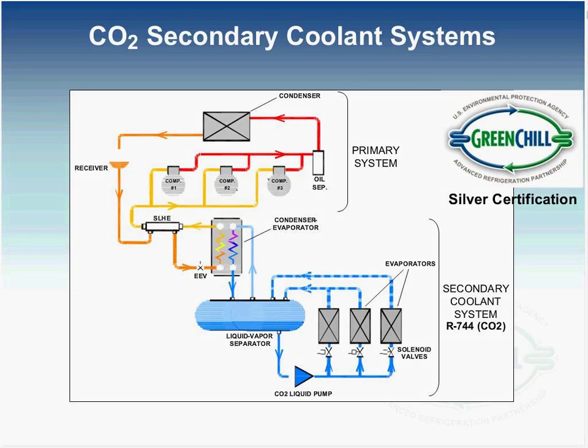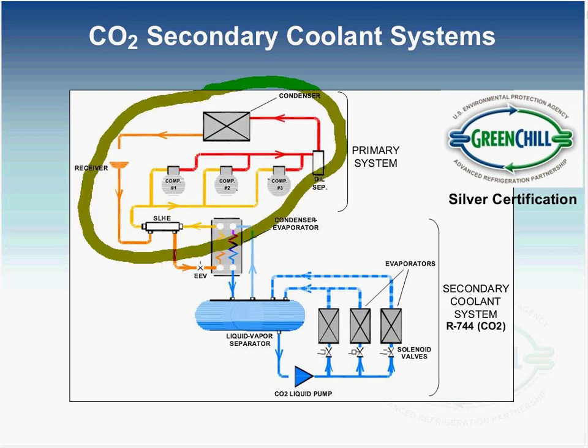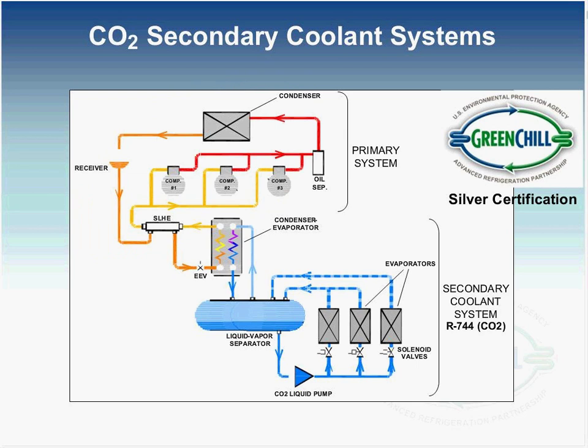So we'll start with a piping schematic here of what the system looks like. In the upper left-hand corner there, you'll see a traditional rack system, and we're not really focused on that so much. That's just like Bruce has been talking about, Travis has been talking about. It's a traditional refrigeration system. It can be whatever refrigerant that you choose, 404A, 507, 407A. We want to focus on the heart of the system, the lower part here that is the CO2 portion of the system. Type systems will give you at least a silver certification in the GreenChill certification program.